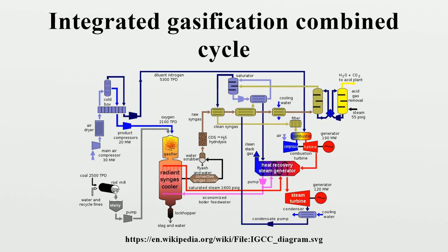With carbon capture, the cost of electricity from an IGCC plant would increase approximately 30%. For a natural gas CC, the increase is approximately 33%. For a pulverized coal plant, the increase is approximately 68%. This potential for less expensive carbon capture makes IGCC an attractive choice for keeping low-cost coal an available fuel source in a carbon-constrained world. In Japan, electric power companies, in conjunction with Mitsubishi Heavy Industries, have been operating a 200T IGCC pilot plant since the early 90s.